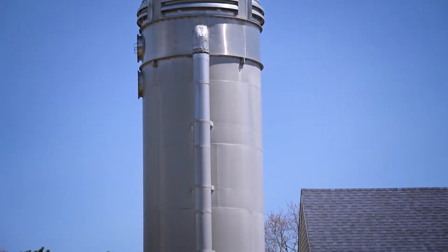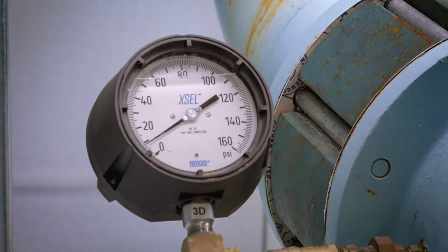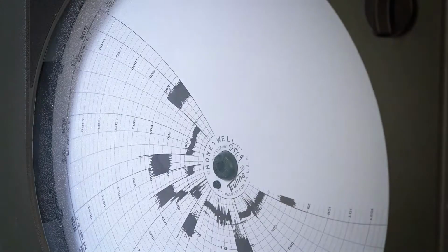At this moment, we're looking at 6 PFASs, and there's an ORSG out, which is a health standard for Massachusetts, that is 70 parts per trillion, and they're talking about going down to 20, but it hasn't happened yet. So what we're trying to do here in Hyannis is to deal with this issue and to position ourselves with pumping out of certain wells and testing so that we can be under 20 as much as we can.